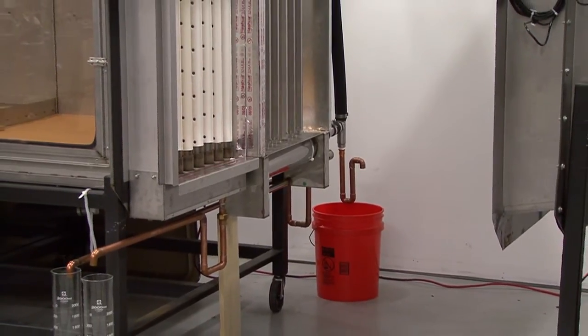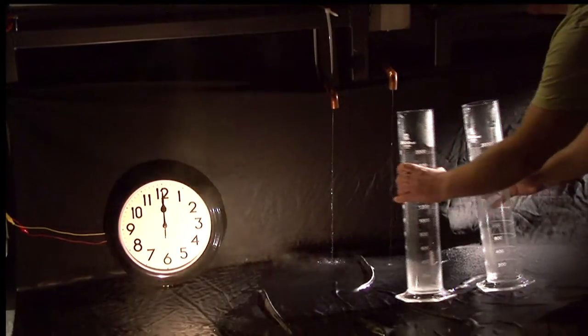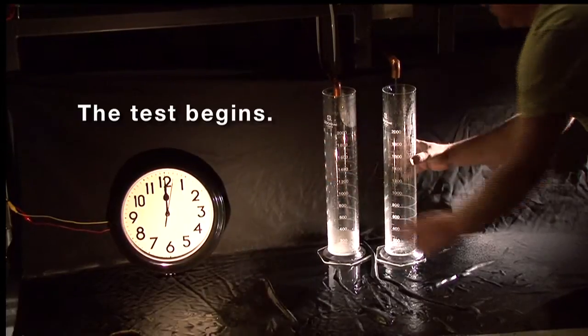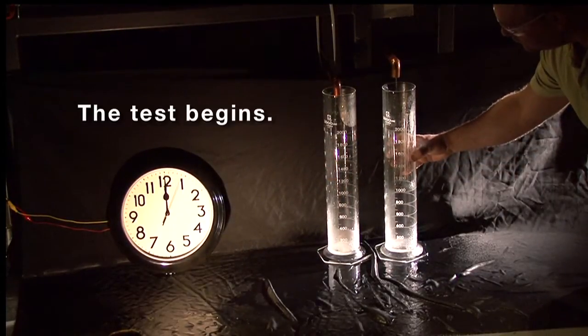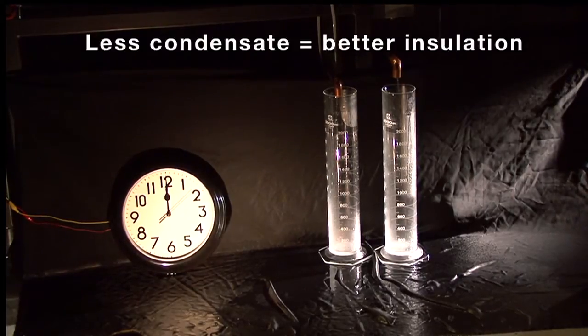To determine which insulation technology performs better, we are collecting condensate produced by each dispersion assembly in graduated cylinders for measurement. The cylinder on the left is collecting condensate from the dispersion assembly with stainless steel shielded air gap insulation. The cylinder on the right is collecting condensate from the dispersion assembly with PVDF insulation.